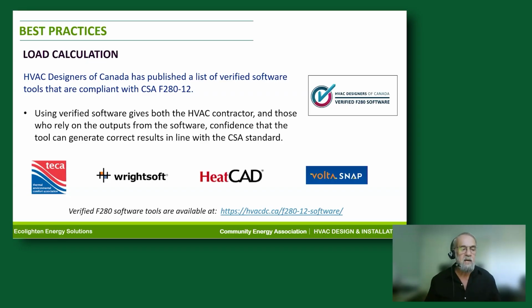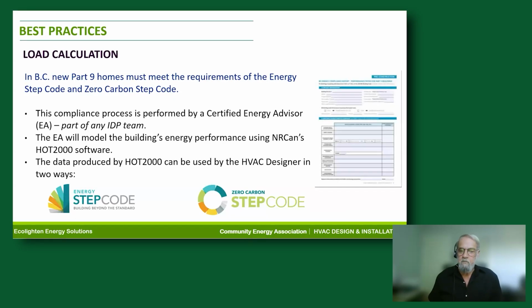And here's a few of them. TECA in BC has a certified F280 load calculating software that is very accessible, doesn't cost much up front, doesn't have a huge learning curve. It's very, very good for contractors. Wrightsoft is another one. It's a little more sophisticated, has a higher upfront cost and yearly subscription, but it's not just doing load calculations. It's also a software that designers use because it does much more than just load calculations, so it has some value if what you're doing all day long is designing systems. HeatCAD is the same as Wrightsoft. And then there's this thing, VoltaSnap, and we'll talk a little bit about that in the next few slides.